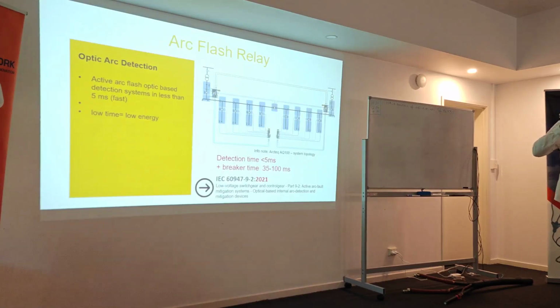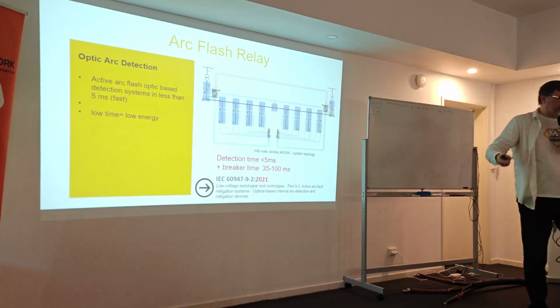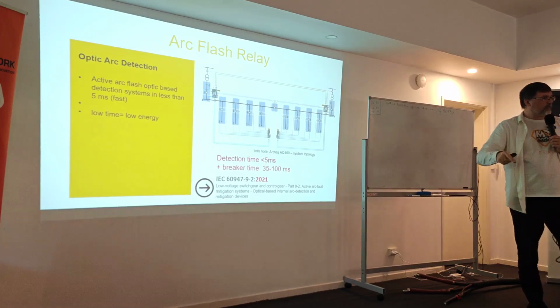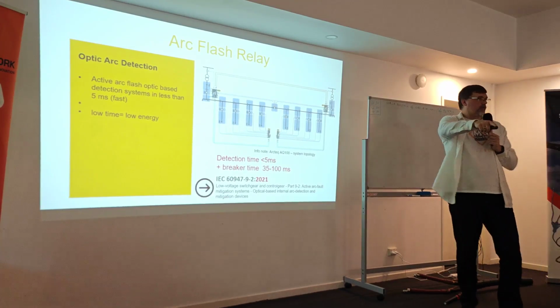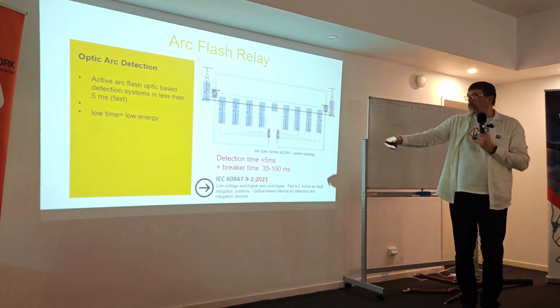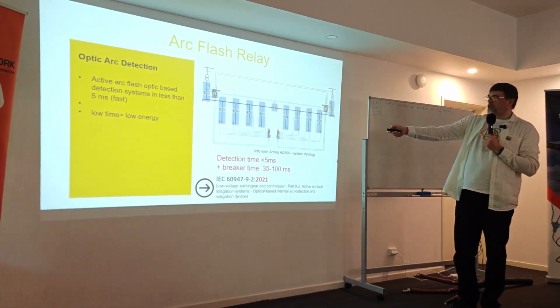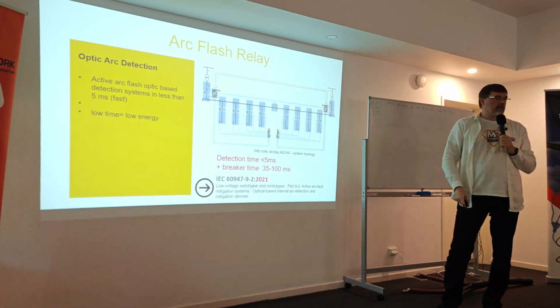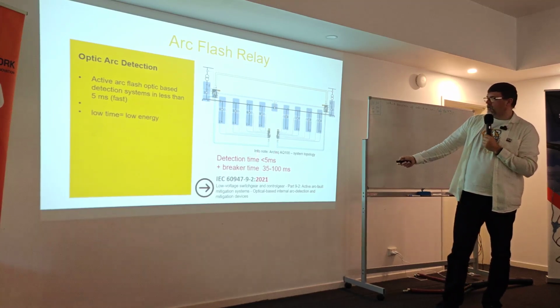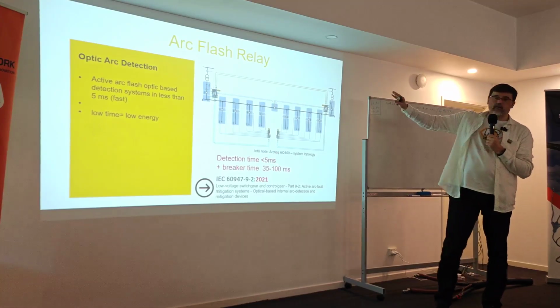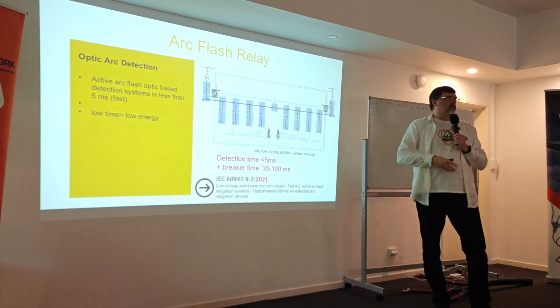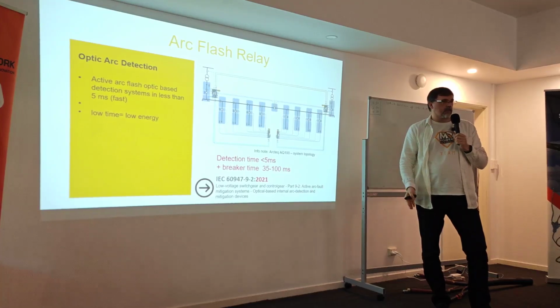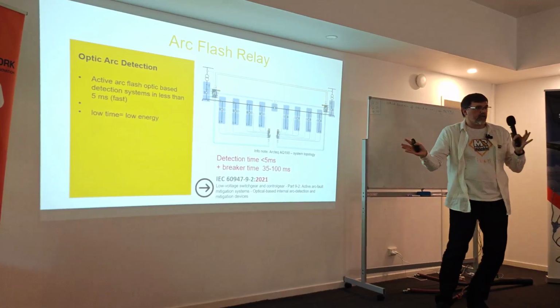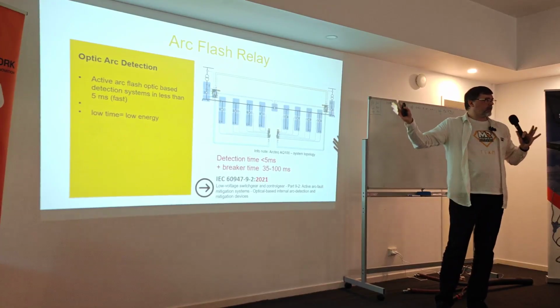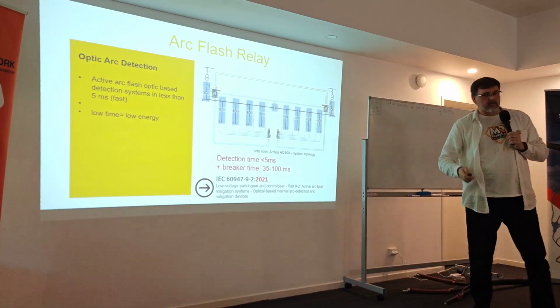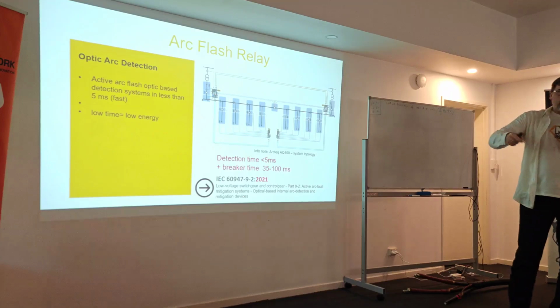The third thing is that you can install a separate system, which is an arc detection system, the optic. That was something that Dave was showing, the relay, that's how it works. So you have a relay with the sensors, you install the sensors, typically optic sensors only. And the difference is that this separate system works quite fast. It doesn't really involve overcurrent protection settings, so you can split selectivity, protection coordination from the arc flash. Now we have two systems. And this can be a separate system or it can be built in the relay.